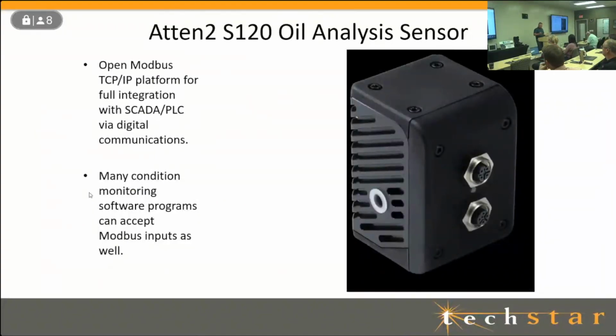The sensor itself, I don't know if y'all can see it on the camera out there, but you can definitely see it there on the graphic. You'll see there's basically two electrical connections on the front. One is for powering up the device. Basic 24-volt DC is all you need to power it up. And the other is a Modbus communications port.